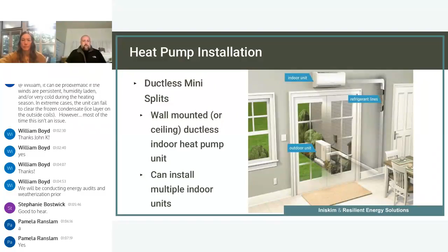And again, as you can see, the lines are insulated and then housed in that plastic conduit, but external temps still play a role. We want to make sure we have that as close to the unit as possible. It gets a bit more difficult when we have lines running to multiple indoor units. It's hard to minimize the length of the run for the refrigerant lines. But in that case, we just try to ensure the outdoor unit is located between the two. And we want to try to keep multiple units on the same exterior wall because of this.